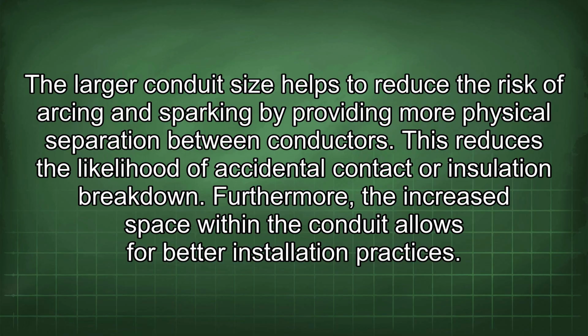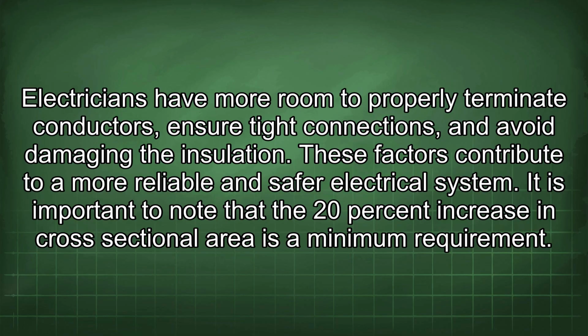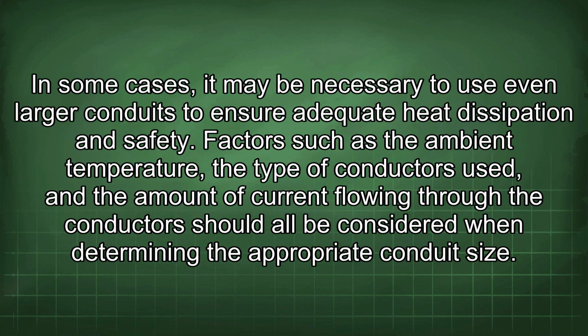Furthermore, the increased space within the conduit allows for better installation practices. Electricians have more room to properly terminate conductors, ensure tight connections, and avoid damaging the insulation. These factors contribute to a more reliable and safer electrical system. It is important to note that the 20% increase in cross-sectional area is a minimum requirement. In some cases, it may be necessary to use even larger conduits to ensure adequate heat dissipation and safety. Factors such as the ambient temperature, the type of conductors used, and the amount of current flowing through the conductors should all be considered when determining the appropriate conduit size.